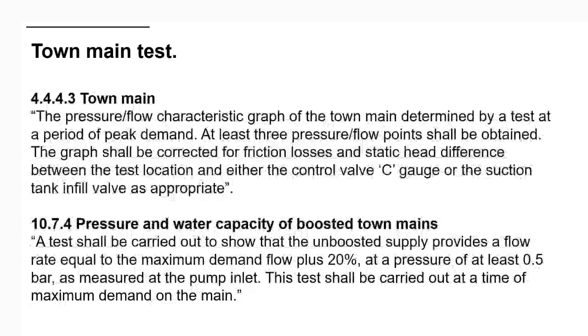Of course, with a boosted town main, we're fixing the pressure problem via a pump rather than from the town main. Again, it's noted to be carried out at maximum demand on the main. So there's a couple of town main tests. Now, these tests would either be carried out by the sprinkler contractor or by the water authority themselves. Again, that's a conversation, and for me, communication is key. You're not supposed to just rock up and start doing tests. Communication is key in terms of talking to your local water authority and explaining what you want to do. They might say, "Yep, that's fine, go ahead and do it," or they might say, "No, we're going to do that ourselves," and you can absolutely book in a slot to do that. And there might be a cost, there might not.